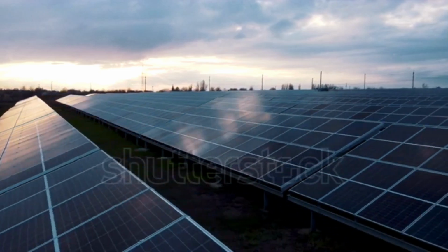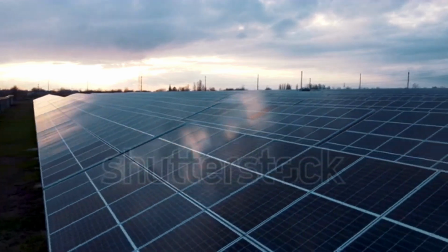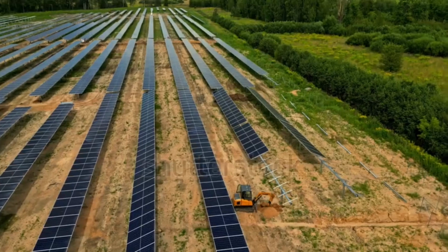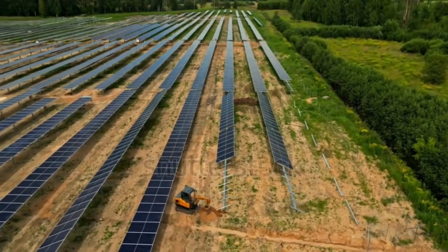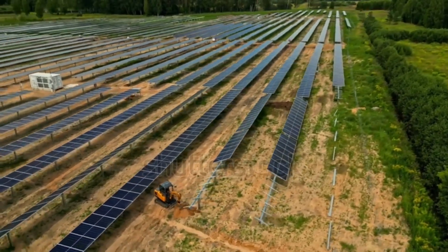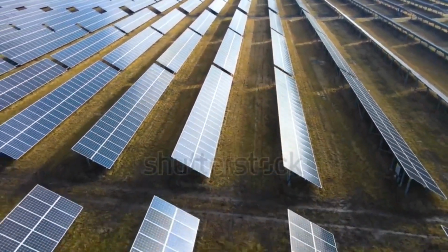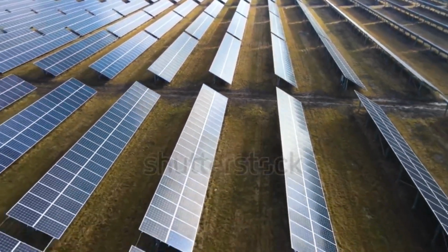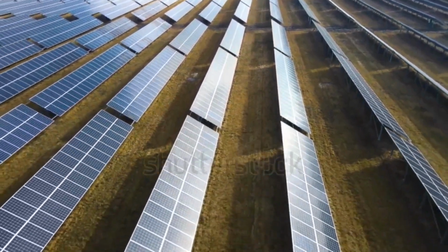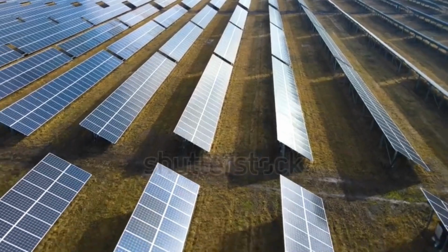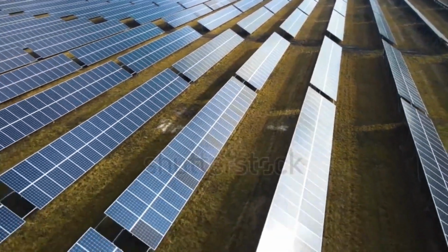6. Thermal management issues. Overheating of panels. Solar panels operate less efficiently when they become too hot. This is a particular concern in areas with high ambient temperatures and insufficient ventilation. If the panels are not adequately cooled, their efficiency and lifespan can decrease. Hot spots. If part of a solar panel gets shaded while the rest remains in sunlight, it can create a hot spot that significantly reduces the lifespan of the panel. This localized overheating can damage the cells and reduce overall output.